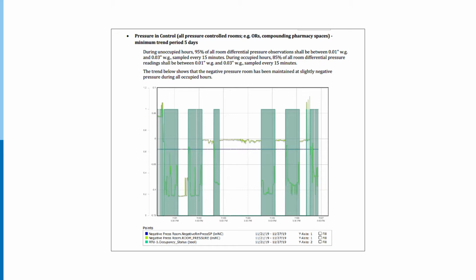The second one is that we have some critical rooms here with pressure controls. Those pressure controls are not cheap, right? So we installed the pressure controls, and they're supposed to be between 0.01 and 0.03 pretty much all the time. And we have an allowance for door openings, so you should be able to see the doors open. And we asked for 5 days of trending on this.